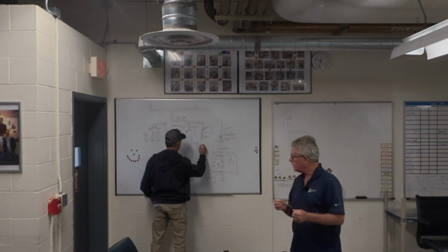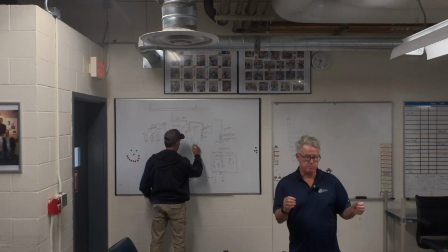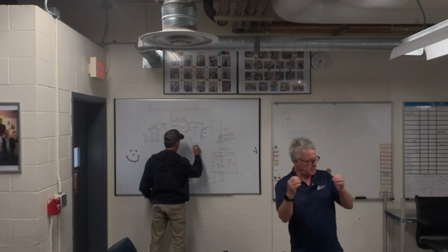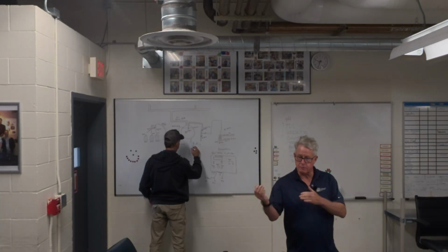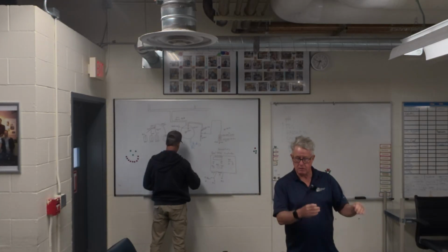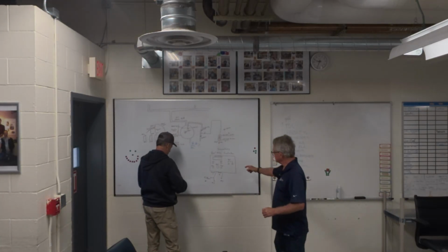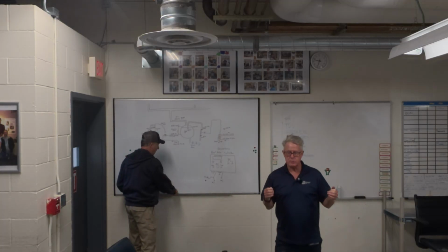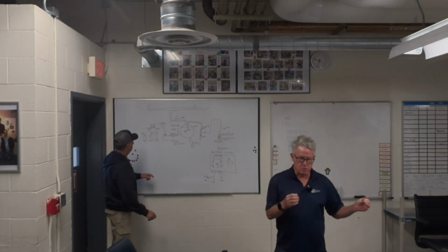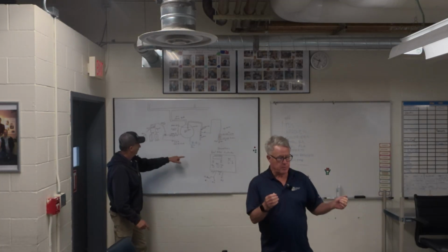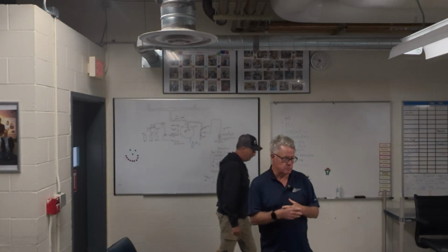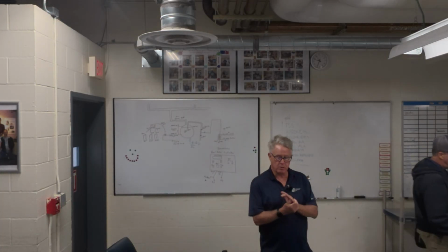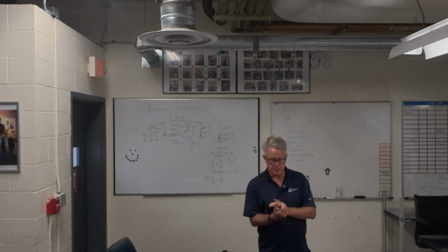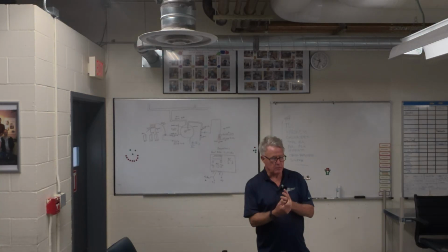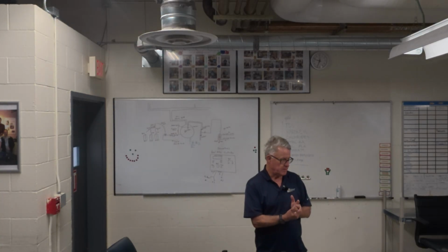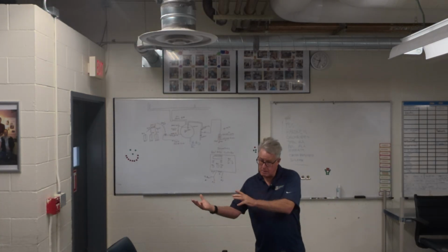Where we're going with this: as the boilers flow water in, we're managing that on a flow meter. It's sending it to a controller. The controller senses how much water is going into the boiler, and then we pump in three associated chemicals to this system. One is a boiler compound, one is an oxygen scavenger, and the other is a steam line agent. So as the boilers are making up water...